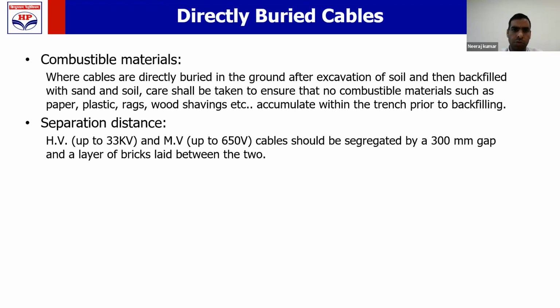First, let us take the most crude method, directly buried cable. I have not made the trench. I have dug the soil and buried the cable inside. ठीक है, bury किया तो किया, but you ensure that while you dig the trench for burying those cables, and you left that trench open for some 1 month. After that, your cable came, and then you put the cable. Then what happened? The paper, plastic, wood, many things accumulated inside that open trench. And over that, you laid the cable. Then the entire purpose of protecting the cable is gone. You should ensure that paper, plastic, rag, wood, whatever flammable material has accumulated inside that open dug trench is removed before you put the cable in that trench, before you fill that trench.